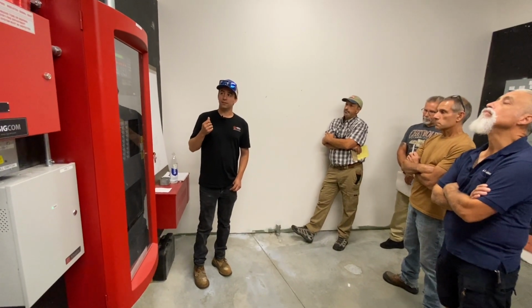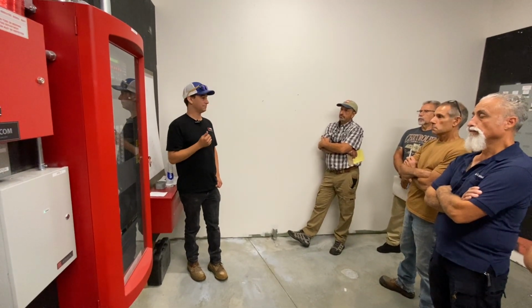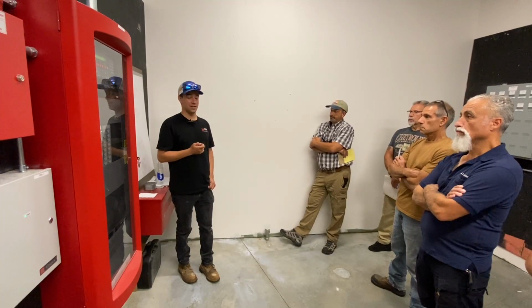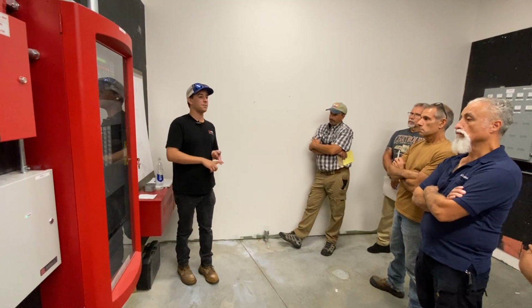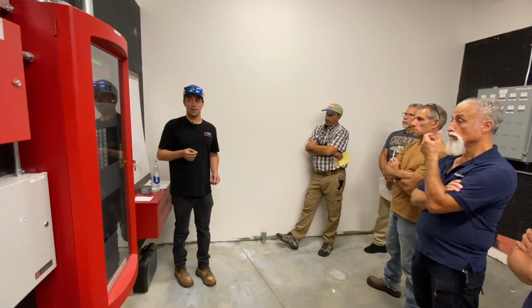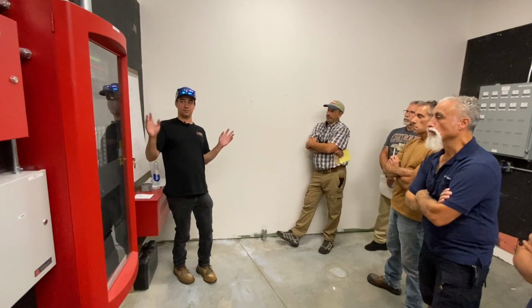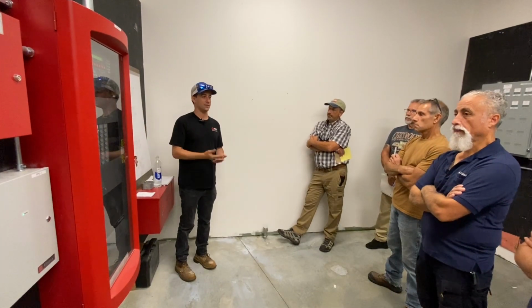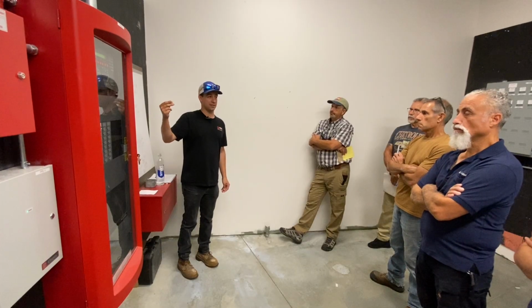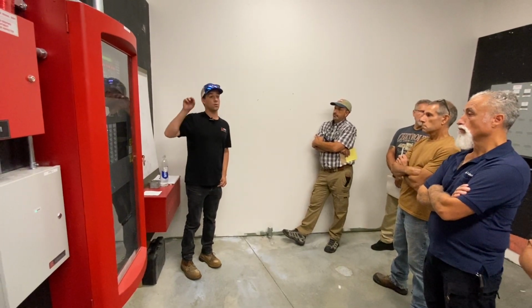The ones that you want to pay attention to are troubles. Troubles are, as you would think, something's wrong with the system. Something's not right. It could be something like a smoke head is not talking, it's loose, it could be bad. It could be anything, all the way down to there's a ground, there's a short. Any kind of problem that may happen is under a trouble. And once again, it flashes a yellow LED. There's no building event that happened because of it. It's all just right here or at the annunciators.